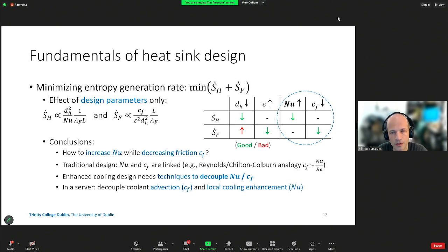this table here is sort of a summary of what happens with heatsink design. So for instance, the effect of the fin spacing or the hydraulic diameter, the DH in this case, if we go to a denser heatsink, right? So DH will go down. That means that SH will go down, which is good, but we get a penalty for additional pumping power, and we see an increase in SF, right? So if you look at the first column over here, this balance between SH and SF will lead to an optimal fin spacing if we just look at that aspect, for instance. So that's kind of trivial.